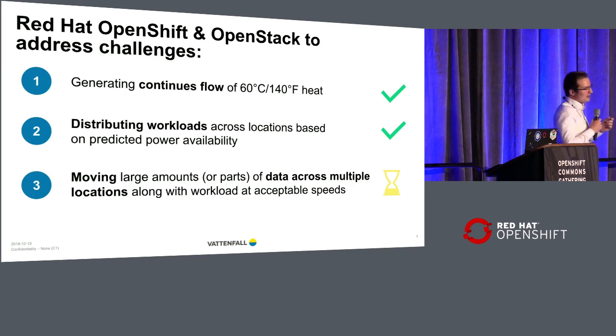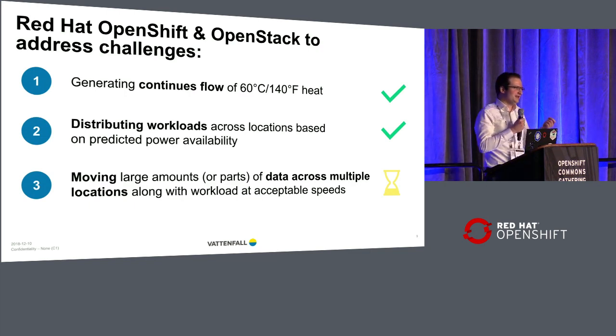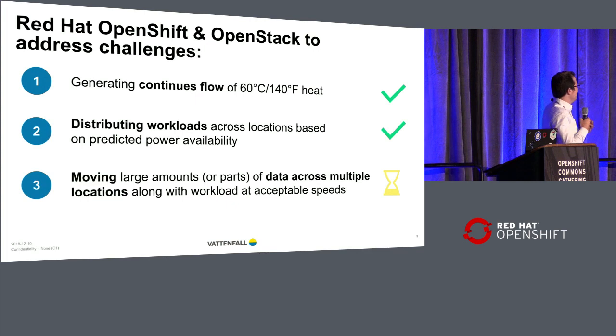The other thing is, if you look at the load curve of a data center, a chip only gets hot when it does something, so you need workloads. A data center doesn't have a flat workload line, it's not running at 100% capacity all the time. If you're lucky, it runs at 40%. So right now, using OpenStack, we had to manipulate the workload.